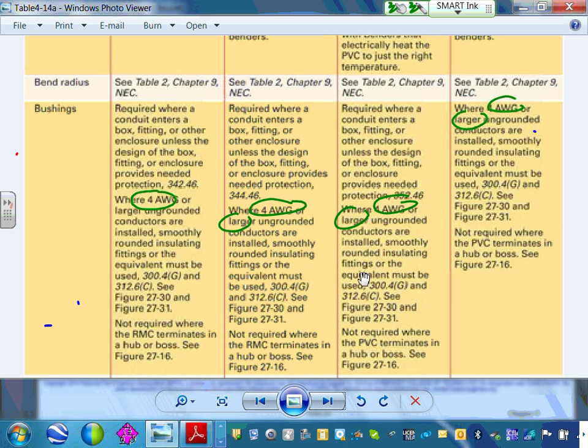So here's what happens. If you bring in a conductor, number 4 or larger, when you pull the conductor, it will damage the insulation, so they have to put that little plastic fitting here to protect the cables. They call them bushings, to protect the cables. Rounded insulated equipment must be used. Not required where the rigid terminates in a hub and so on. So for the most part, they're all required.